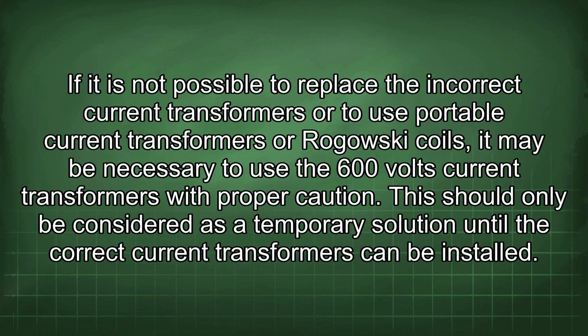If it is not possible to replace the incorrect current transformers or to use portable current transformers or Rogowski coils, it may be necessary to use the 600 volts current transformers with proper caution. This should only be considered as a temporary solution until the correct current transformers can be installed.